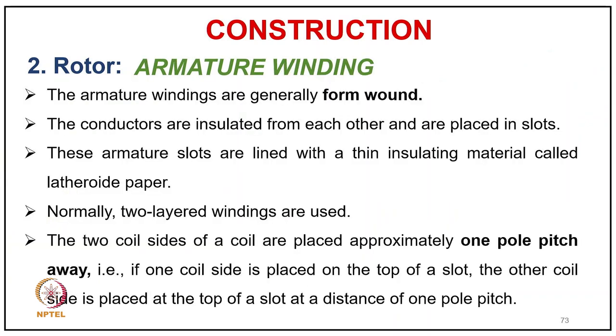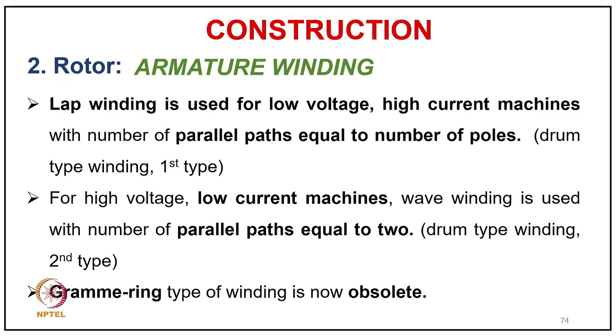Armature windings are generally form-wound; conductors are insulated and placed in slots lined with leatheroid paper. Two-layer windings are normally used. The two coil sides of a coil are placed approximately one pole pitch apart — one in the north pole region at the top of a slot and the other in the south pole region at the bottom of a slot one pole pitch away. Two types of armature winding exist: lap winding (low voltage, high current, parallel paths equal to number of poles) and wave winding (high voltage, low current, two parallel paths).